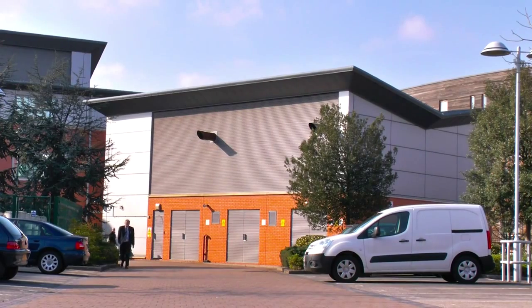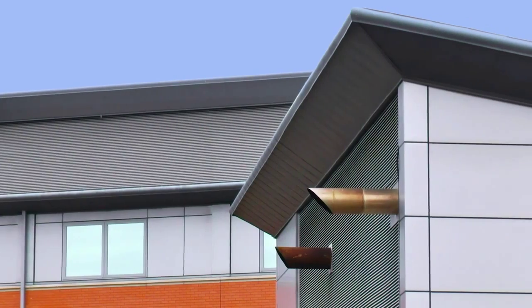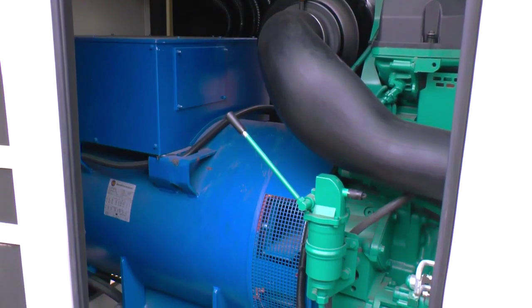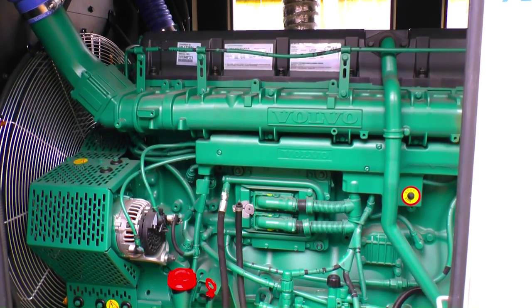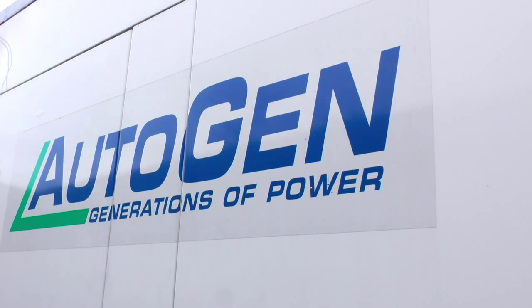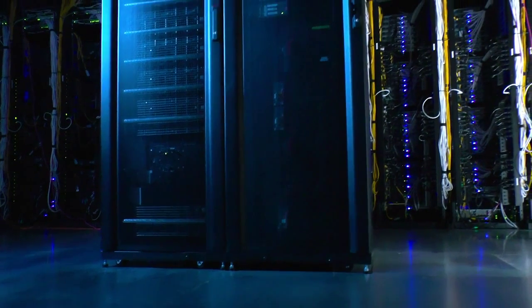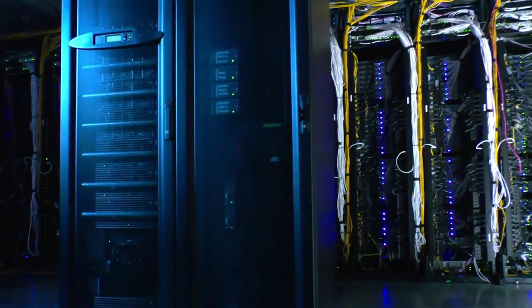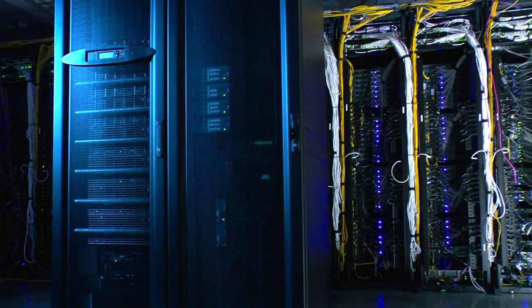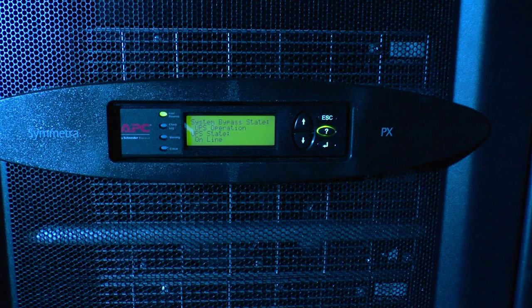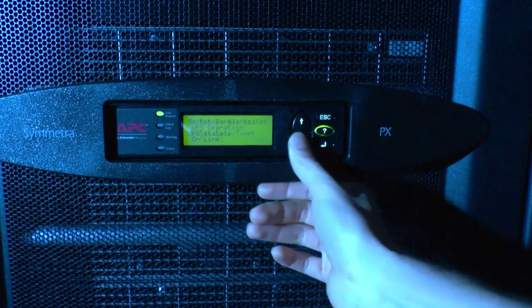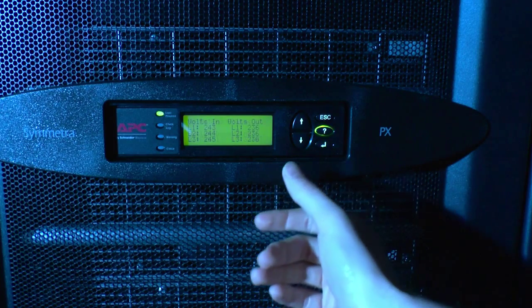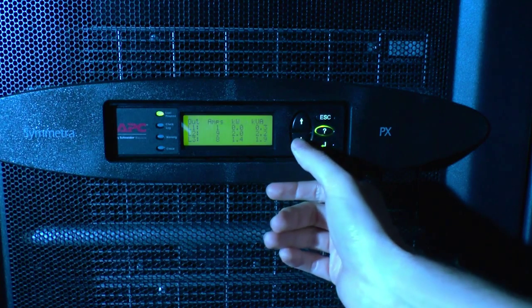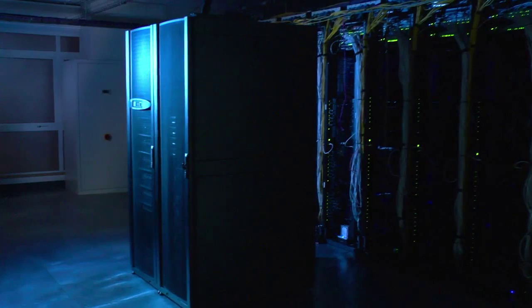If there's a loss of power to the facility, we'll keep everything running by means of on-site generators with enough fuel to run them for at least 5 days. All servers are protected by our UPS system, which stands for Uninterruptible Power Supply. This system not only cleans the incoming power, but it's also used to bridge the gap between power cut and the generator starting, which takes about a minute.